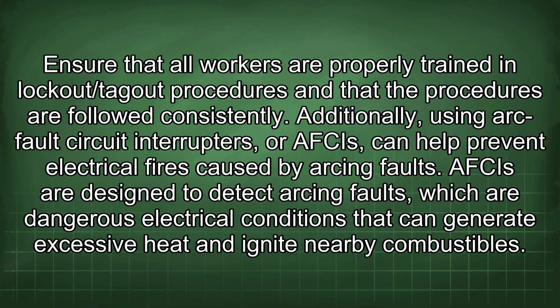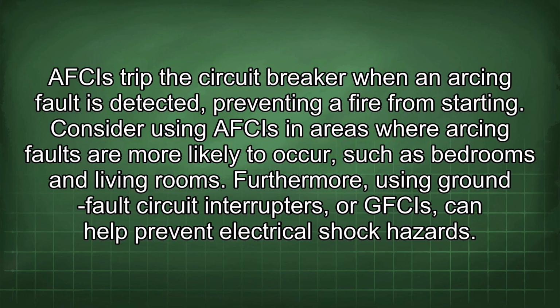consistently. Additionally, using arc fault circuit interrupters, or AFCIs, can help prevent electrical fires caused by arcing faults. AFCIs are designed to detect arcing faults, which are dangerous electrical conditions that can generate excessive heat and ignite nearby combustibles. AFCIs trip the circuit breaker when an arcing fault is detected, preventing a fire from starting. Consider using AFCIs in areas where arcing faults are more likely to occur, such as bedrooms and living rooms.